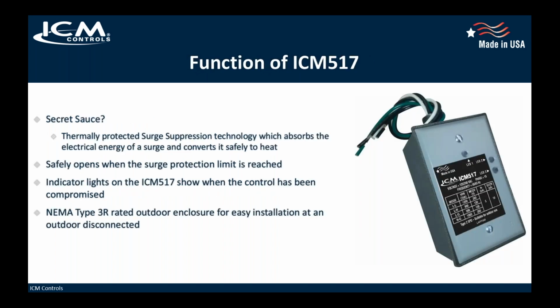So, the functionality of one of our main line single phase surge suppressors. This is the one we're offering now. We will have a wider line of surge suppressors coming up, but right now this is our main line surge suppressor. And the question is, how does this work? What is the secret that keeps these voltage spikes from getting through? We use what they call a thermally protected MOV, metal oxide varistor, which suppresses the surge. It's not in series with the product line. It's in parallel with the main line, and we're monitoring that voltage.